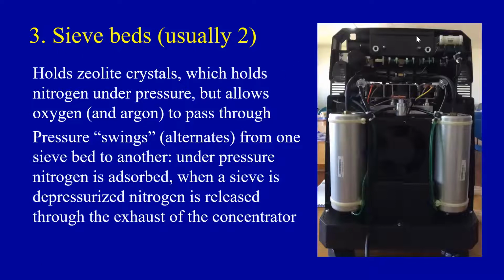The third part is probably the most important part, and I've taken the back off a concentrator to show you this. These are the main parts of a concentrator, and they're called the sieve beds. They look like cylinders, but inside them they've got a special crystal, and the crystals are called zeolite crystals, and they're unique crystals because they can absorb nitrogen under pressure. When the compressor is blowing gas into the sieve beds, when it's coming down here and blowing into this sieve bed, then nitrogen absorbs or sticks to the crystals, and that means that oxygen can go all the way through.